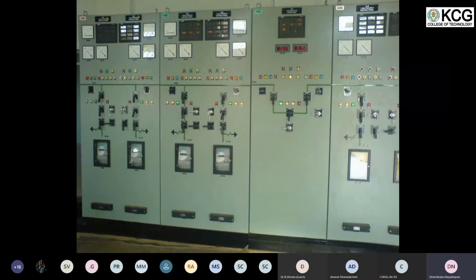So this is the list of equipments available in the control panel, or the functions of a control panel. It is used to control the isolators and breakers, and to control them, you need a clear indication of many things. To give that indication, we have all these equipments. These are TTBs, test terminal blocks. You can open this, isolate the current and voltage from the field, and you can inject secondary values directly here and test the energy meter. We cannot open the CT secondary. So there is a looping available, by which the CT secondary would be shorted, and then we can work in the system.